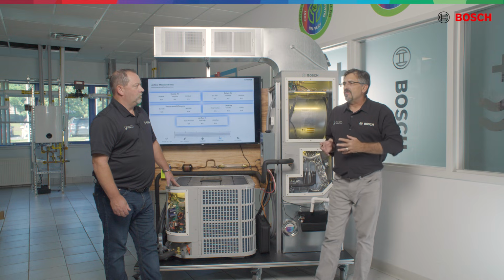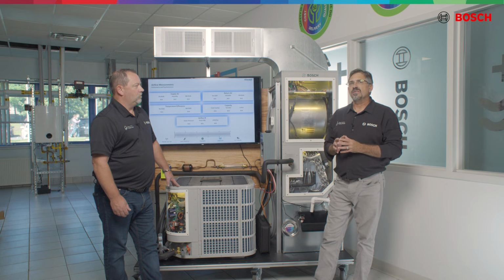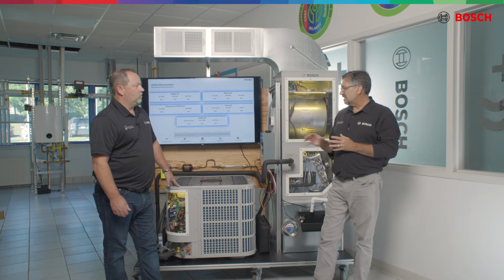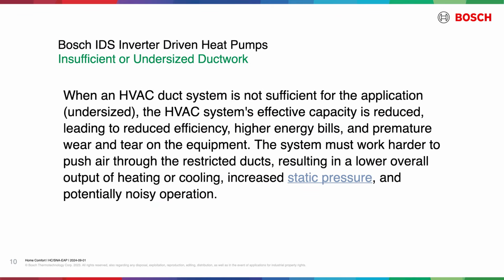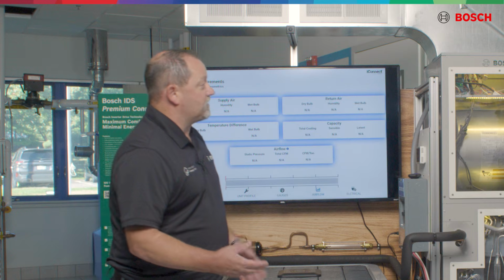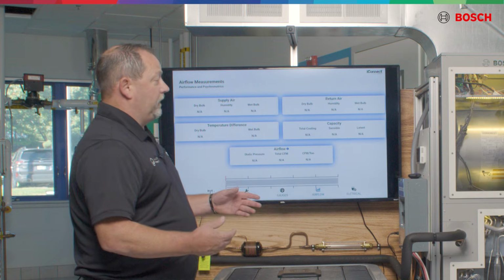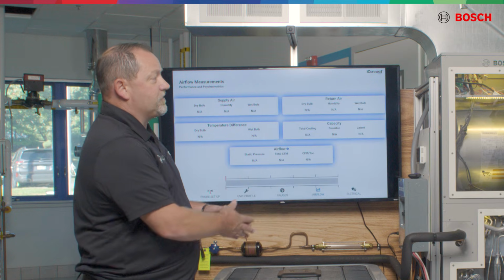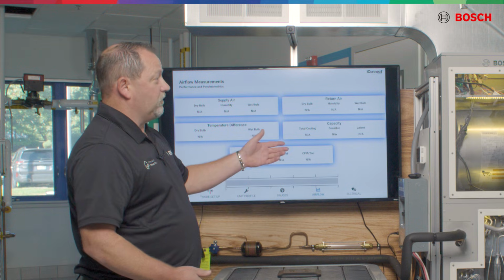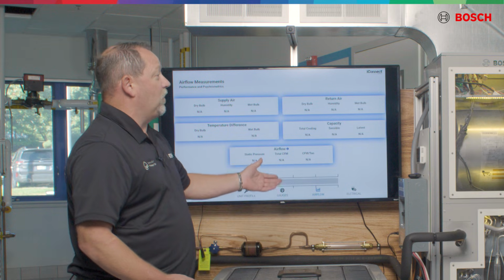When we discuss part failures, one of the number one things that causes a part failure is the ductwork. The reason why is the system works harder and is stressing the compressor, stressing the fan motor to overcome whether it's static pressure, refrigerant charging issues. So basically what I'm hearing you say is I can't install this system on existing ductwork. Do I got to make some changes to that ductwork? And if I don't, what's going to happen?